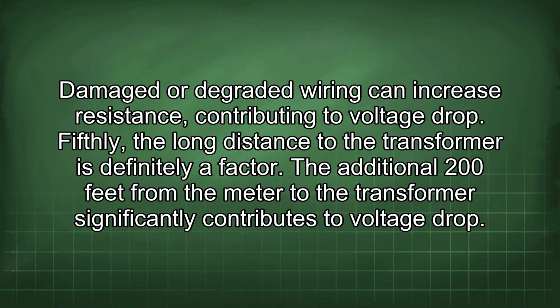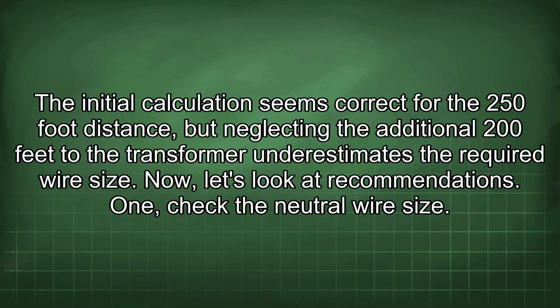Fifthly, the long distance to the transformer is definitely a factor. The additional 200 feet from the meter to the transformer significantly contributes to voltage drop. The initial calculation seems correct for the 250-foot distance, but neglecting the additional 200 feet to the transformer underestimates the required wire size. Now let's look at recommendations.